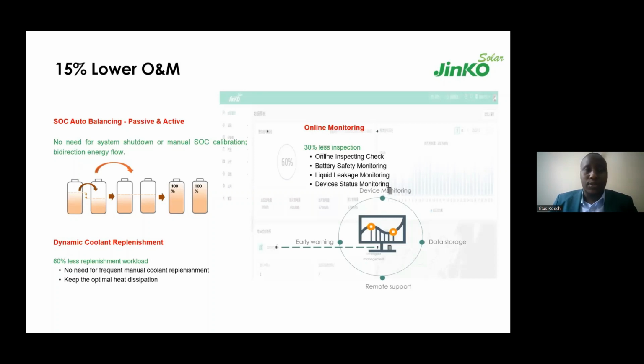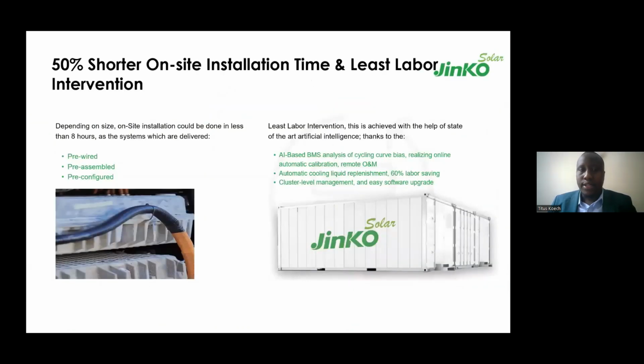The automatic calibration technology also allows for bidirectional energy flow between the battery cells, from one battery cell to the next. And apart from the EMS, we have also integrated a monitoring system specifically made for the battery containers, where you can access online inspection checks, and for O&M purposes, check for any leakages, and check the battery cells, should there be any defects in any of the battery packs or battery cells.